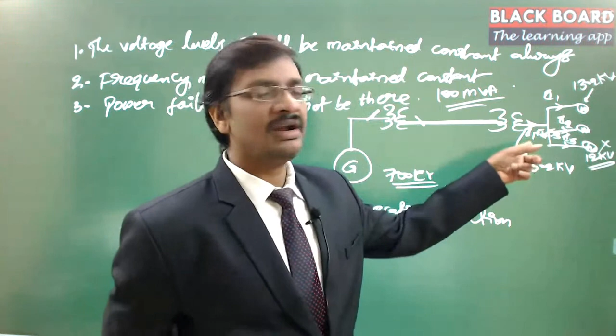That means earlier we were getting only 12 kV, now we got 13 kV, because of the reduction in power consumption from the load centers. This is quite dynamic, because it depends on the applications these motors are used for, so it keeps changing dynamically. Hence, if you design for 12 kV, 13 kV will come and it will spoil the motor. So this is one more important problem.